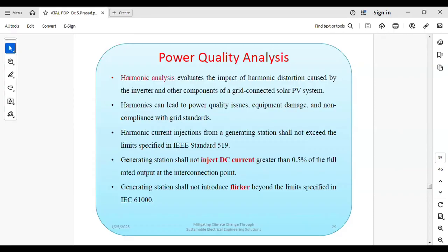Okay, so therefore we perform a harmonic analysis to evaluate the impact of harmonic distortion caused by the inverter and other components of the grid connected solar PV system. Basically, power electronics devices will create distortion in the power system. Harmonics are injected due to power electronics devices, some nonlinear loads also, and because of the transformer operating scenario also, at what point the transformer is operating. Okay, so because these are the sources of harmonics, we conduct harmonics analysis, and you have to get it approved that it is within limit.